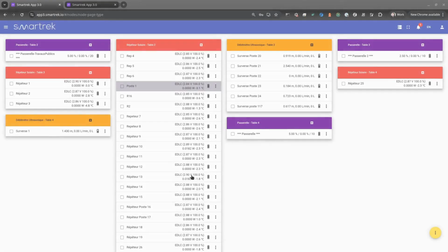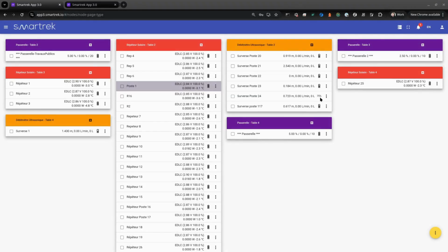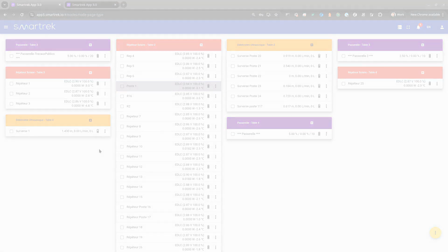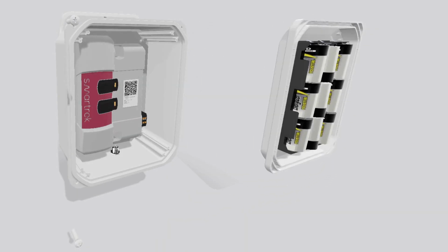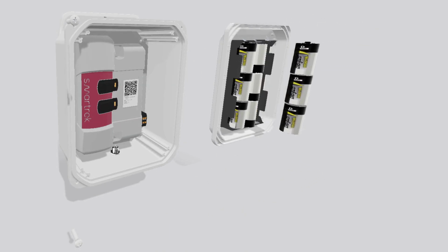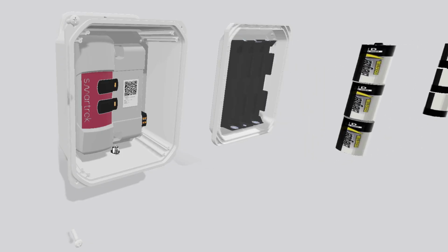Next, navigate to the Devices page. Check the battery level of all your overflow monitoring sensors. Batteries should be replaced at 40% to avoid any data interruption during flood season. Remove the sensor from the manhole to replace the batteries. Then, unscrew the lid of the waterproof enclosure using a star head screwdriver. Open the lid carefully, making sure not to damage the wires.